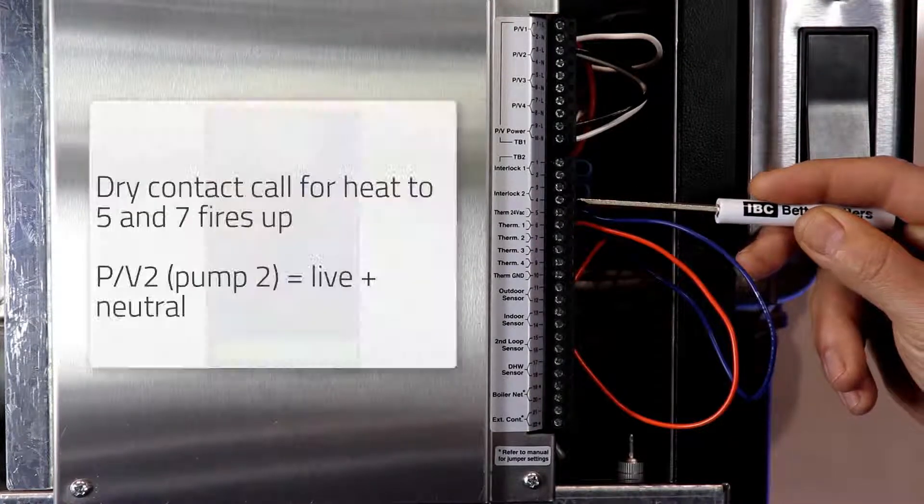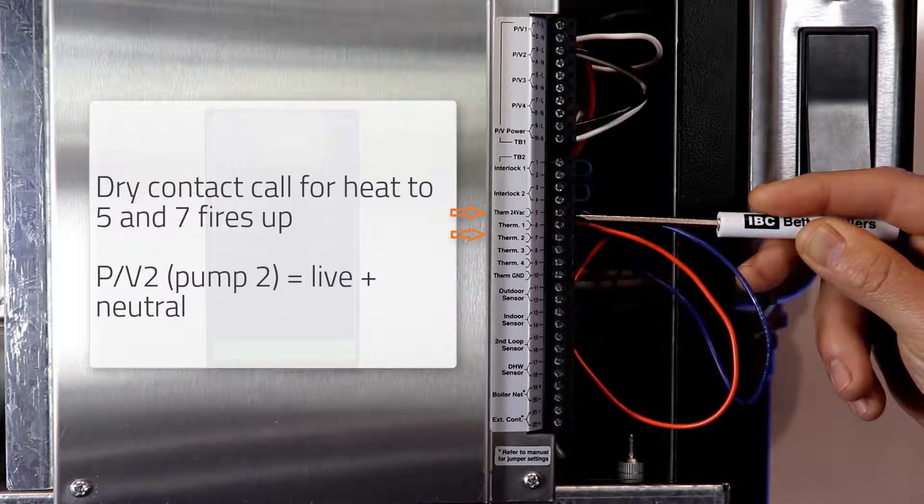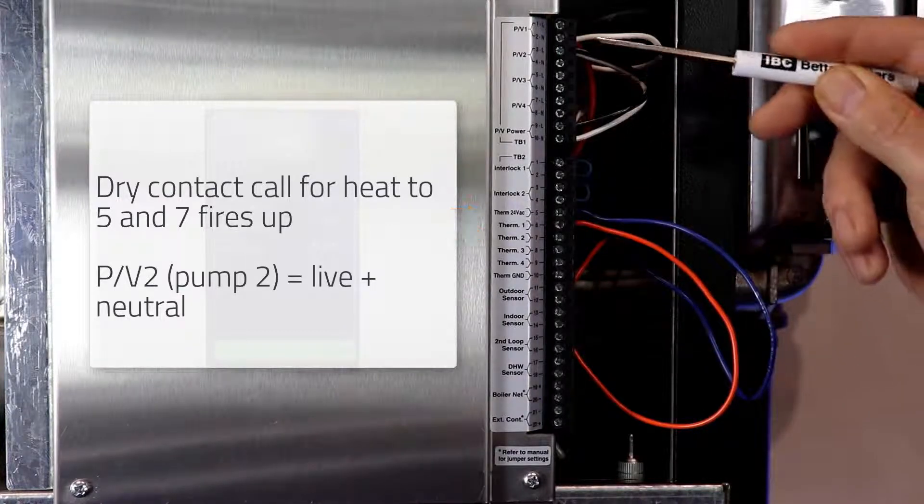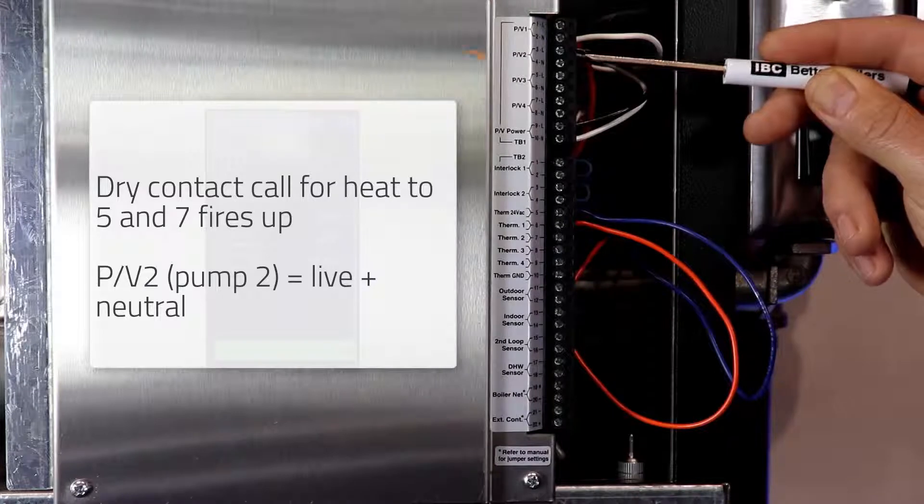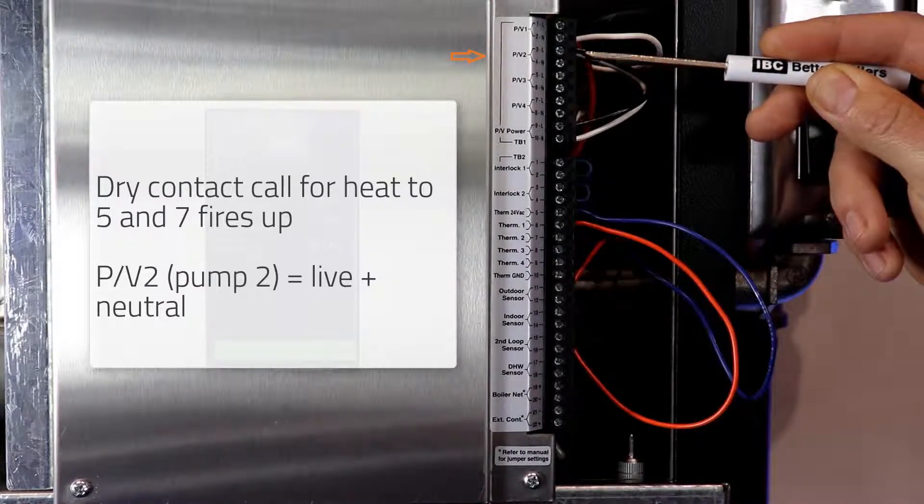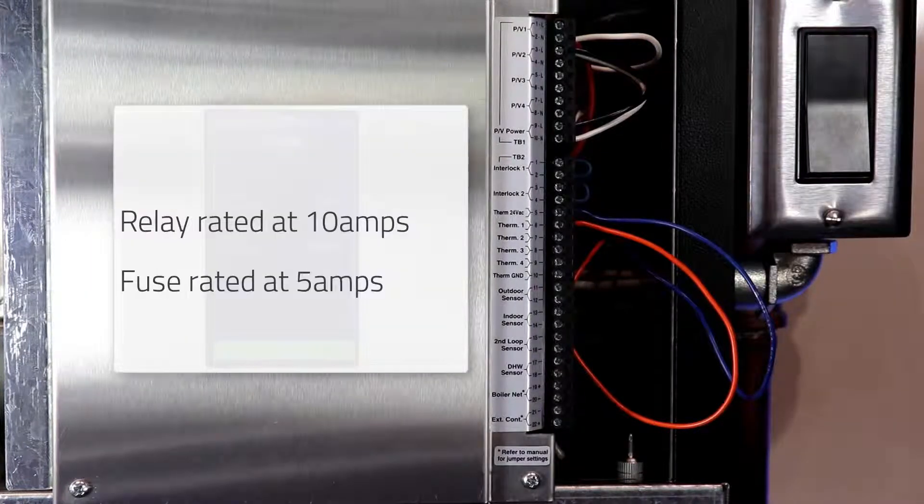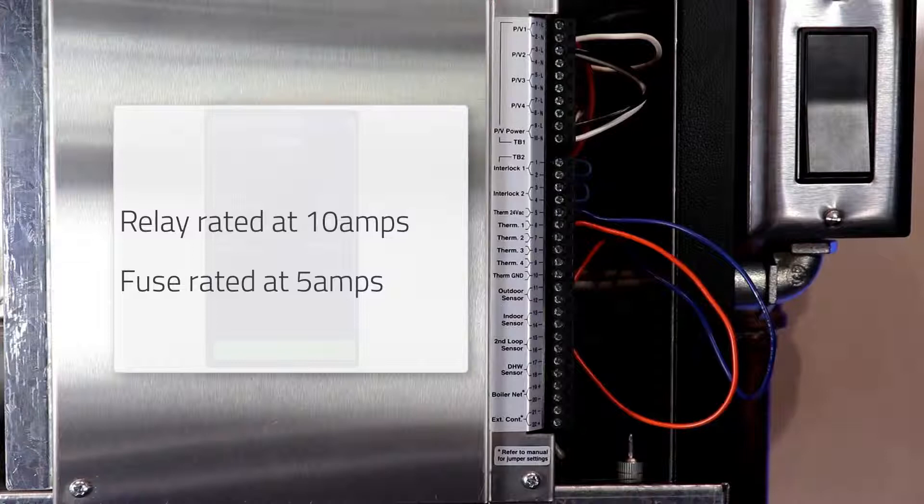Correspondingly, if you wire a dry contact to 5 and 7, when that dry contact closes, it will energize the PV2 relay on the TB1 terminal with a live and a neutral for the pump. The relay on the board is rated at 10 amps and the fuse for that particular pump is rated at 5 amps.